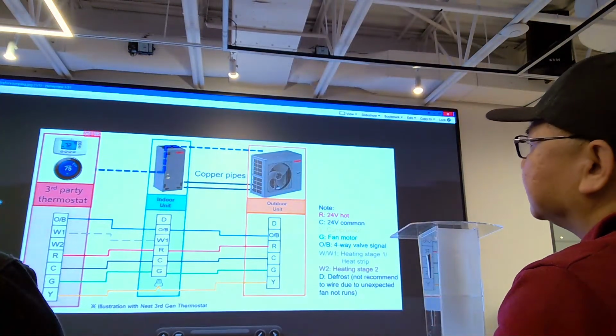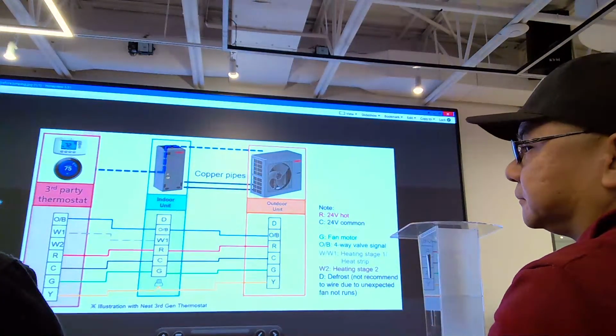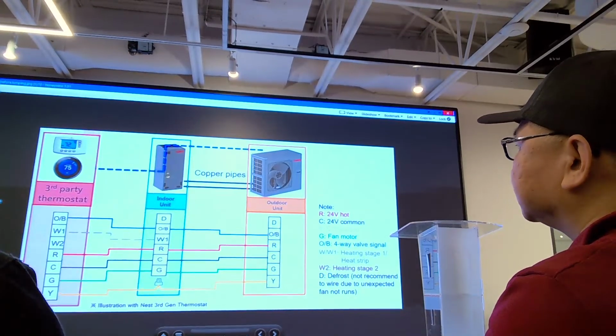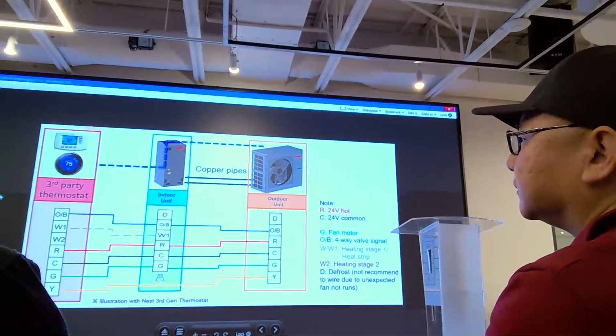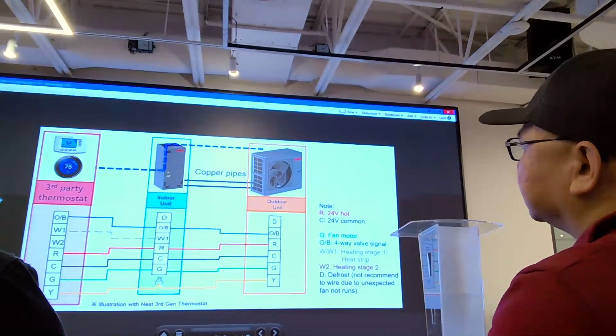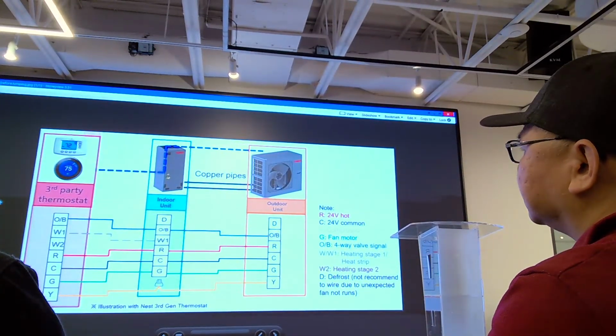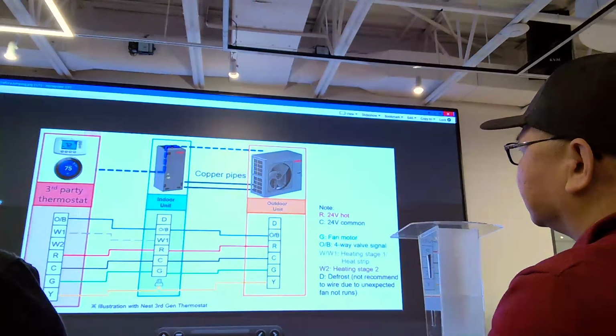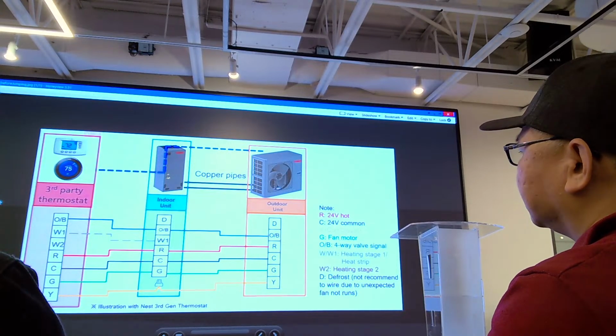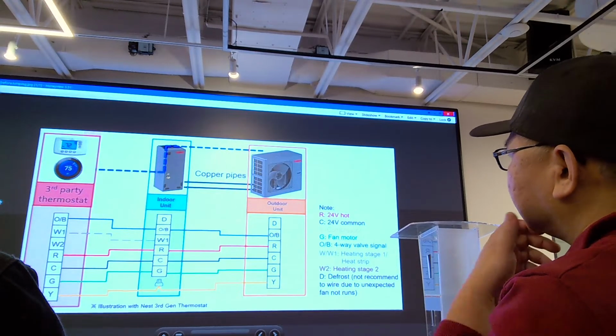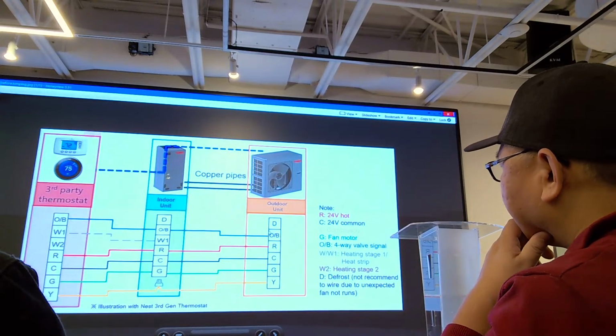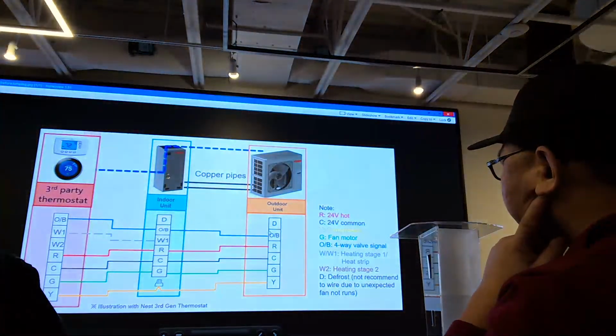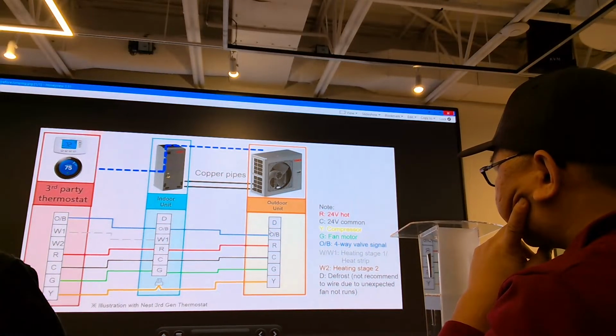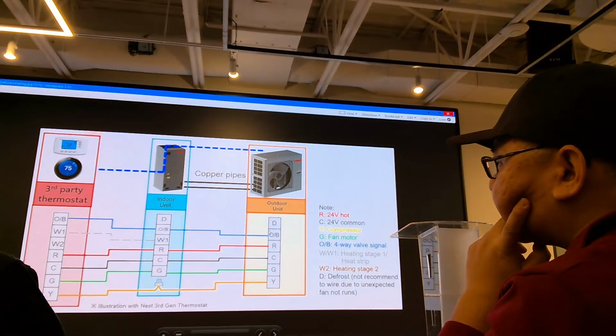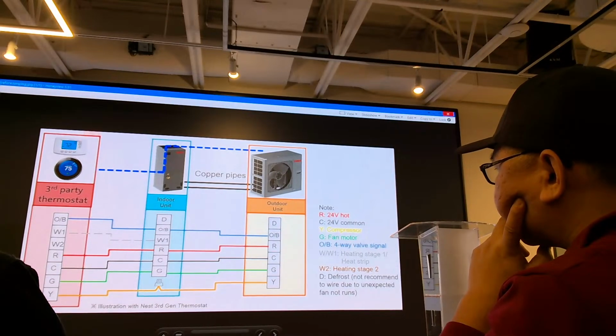And here is also another wiring. So let's assume that the customer just complains, why is my equipment not heating? It's always in cooling, even if I set it to heating from the thermostat. What will you check? Which wire? Yes, wire OB. So in our device, we should make the valve energized. If it is no power, that means it is cooling mode. And on the job site, you can also jump the wire from R to this B, which is this one.